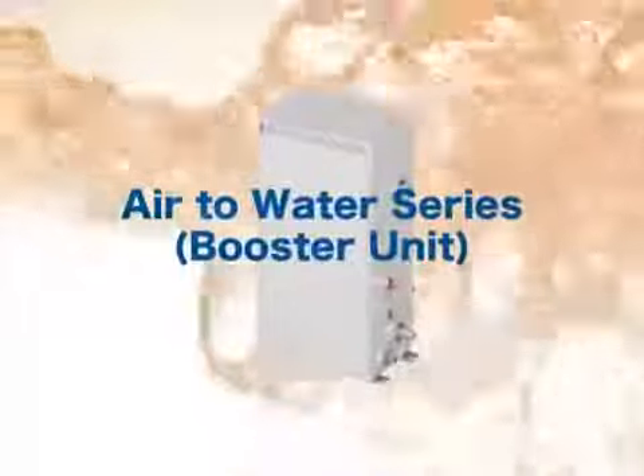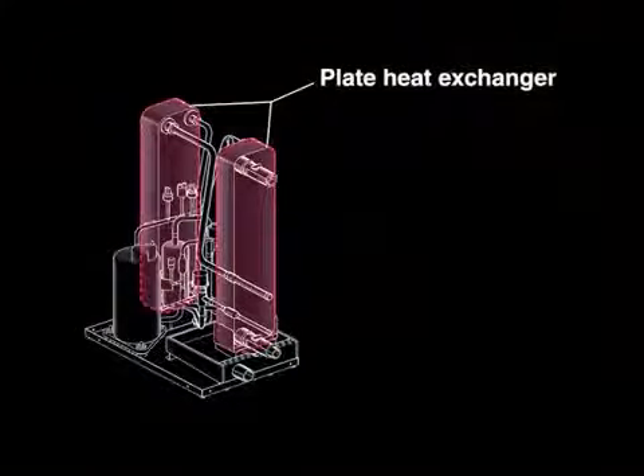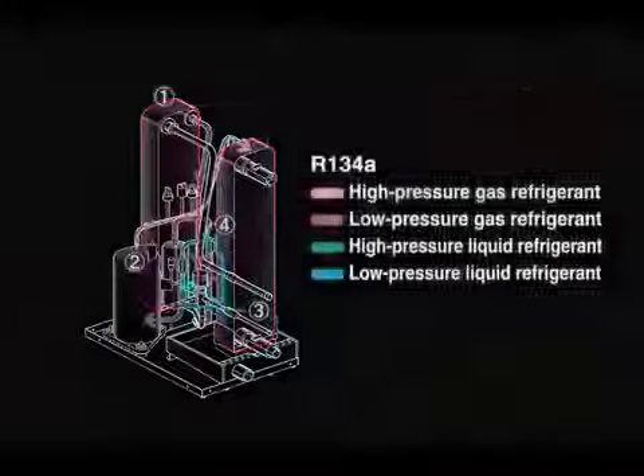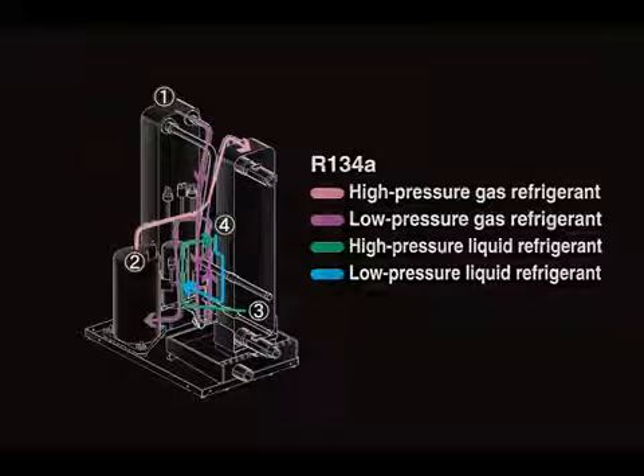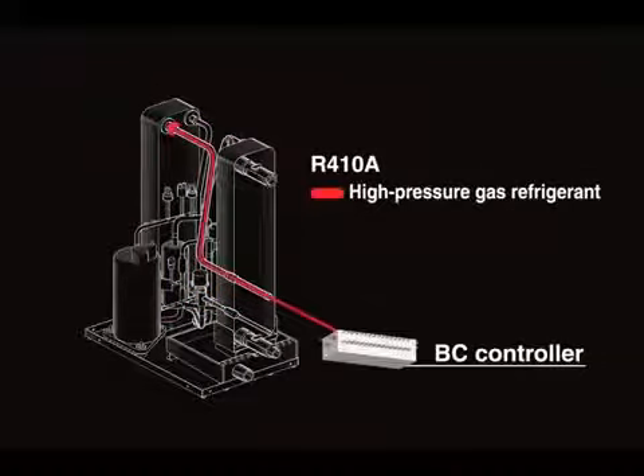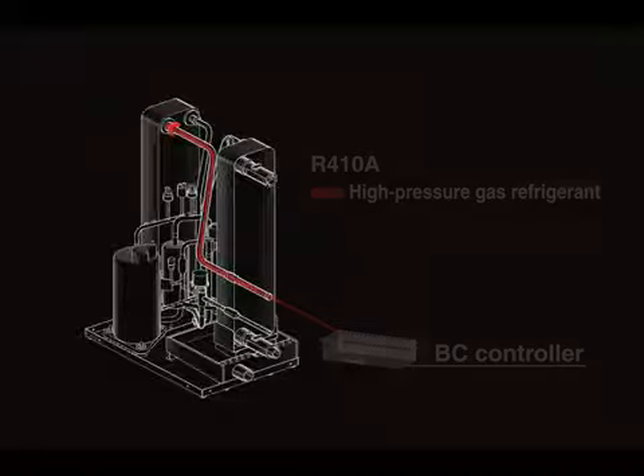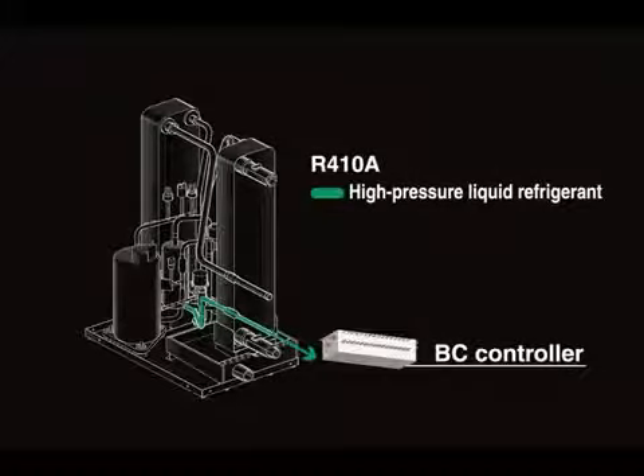Booster unit is connected to BC controller with refrigerant pipes and to the water tank with water pipes. There are 2 plate heat exchangers inside the unit where the refrigerant of R134A circulates. High-pressure R410A gas refrigerant is delivered from the BC controller. Low-pressure R134A liquid refrigerant circulating through the first heat exchanger is heat exchanged to become low-pressure gas refrigerant, and high-pressure R410A liquid refrigerant circulates back to the BC controller.